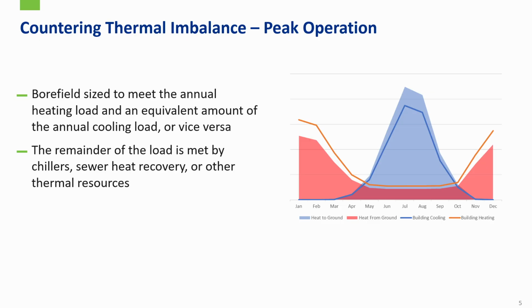Generally, the most simple and basic form of a hybrid system is a peak operation scheme. You track the condenser water temperature in your system, and whenever that condenser water moves outside of a set range, high or low, you kick on some form of on-demand thermal resource, whether that's a boiler, a chiller, or a dry cooler, to bring that temperature back into the range you want.